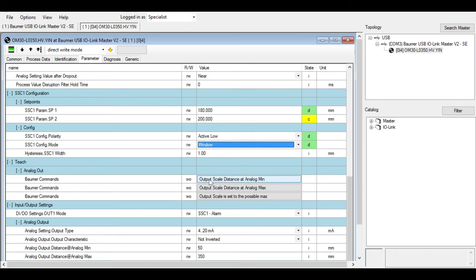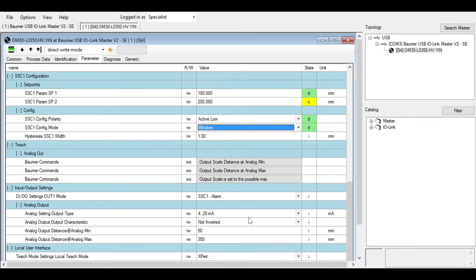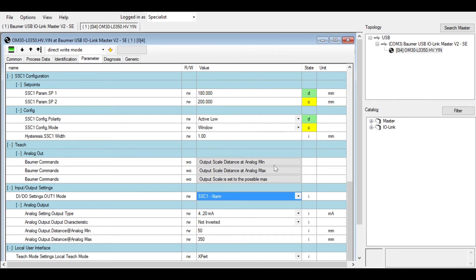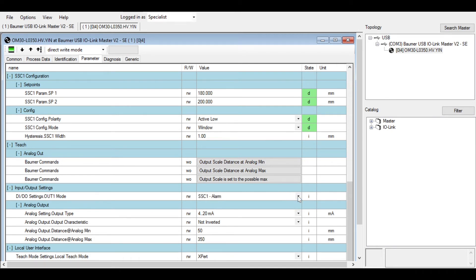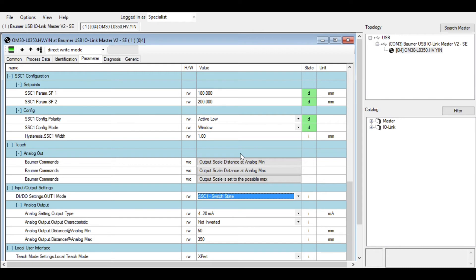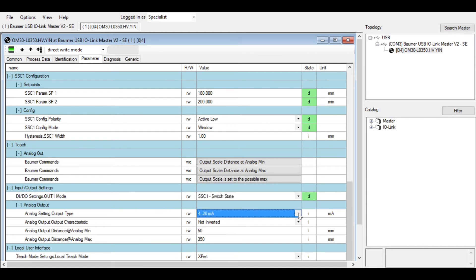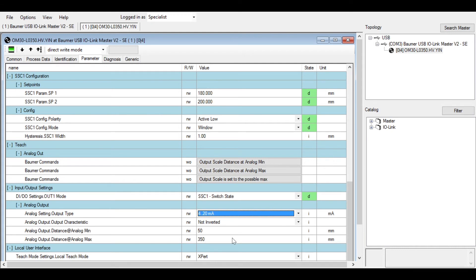You can set the range for the minimum scale of the analog output and the maximum scale of the output. You can say what you want the physical output to give you an output for: is it the alarm, or is it you want it as a switch thing? The switch state is what we would want if we wanted to switch the sensor on and off for the physical output outside of those points, rather than the alarm state. The analog output can be set as well, and that can be the scale that you want of 4 to 20 milliamps or 2 to 10 milliamps. Of course you can set where you want the analog range to start and finish.